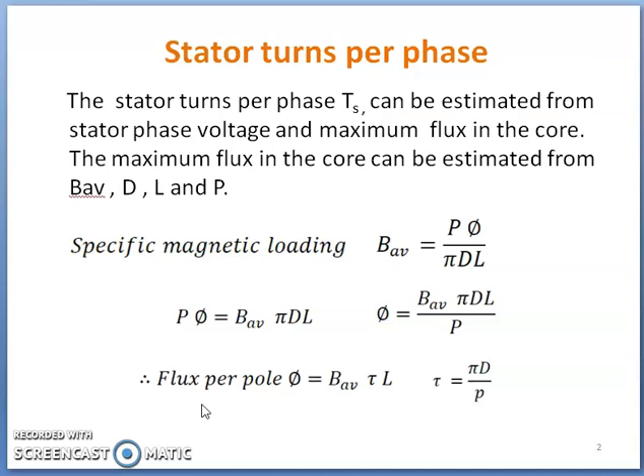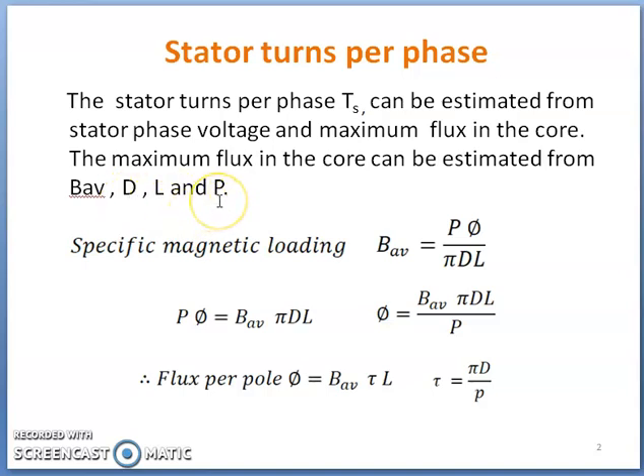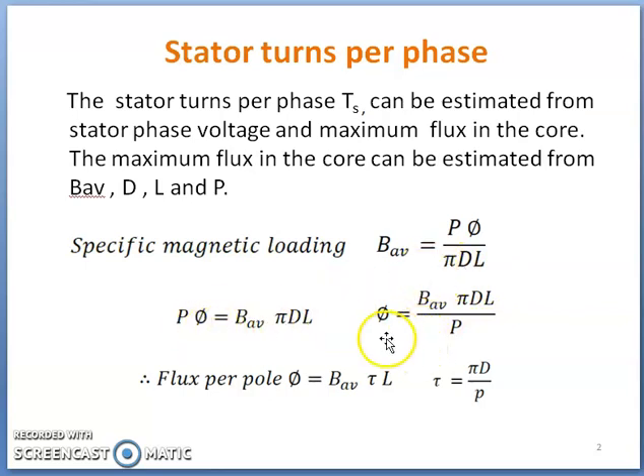The stator turns per phase Ts can be estimated from the stator phase voltage and maximum flux in the core. The maximum flux in the core can be estimated from specific magnetic loading and main dimensions of the machine. Specific magnetic loading B_average is given by B_average equals P*phi divided by pi*d*l, so P*phi equals B_average*pi*d*l. Then flux per pole phi equals B_average*pi*d*l divided by P, and tau (pole pitch) equals pi*d by P, so flux per pole phi equals B_average*tau*l.